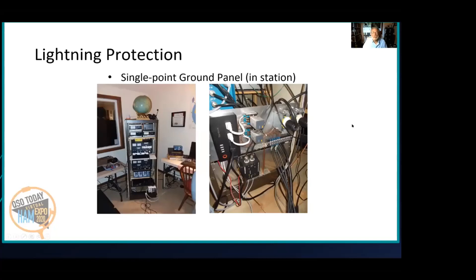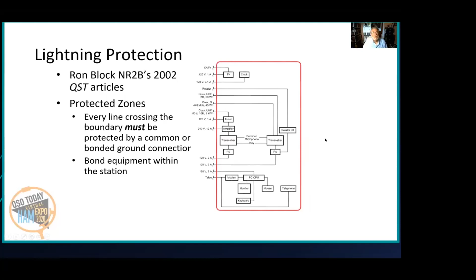You should definitely look at Ron Block's lightning protection articles. He talks about the idea of a protected zone where everything inside this zone, every wire that crosses the zone line, has to be protected by a common or bonded ground connector. If you don't do that, then the one that you don't protect will be where lightning gets in. And bond all your equipment together in your station as well.